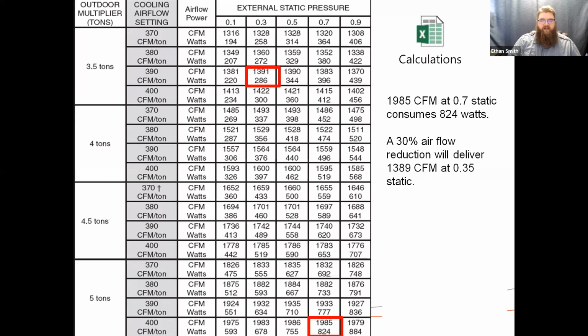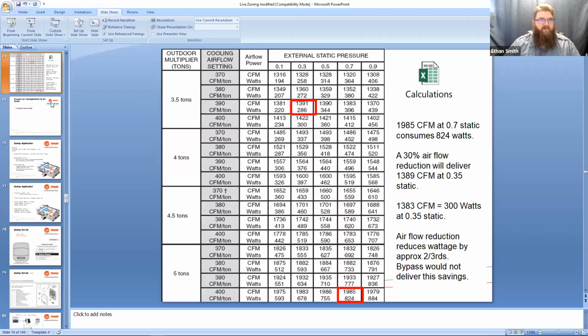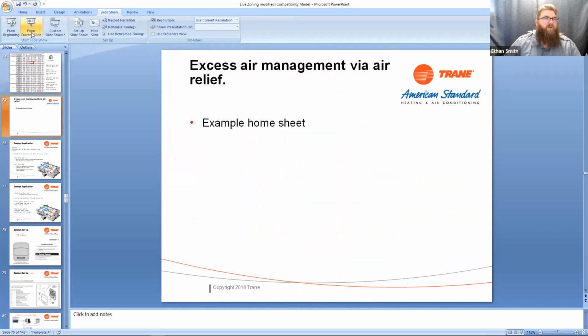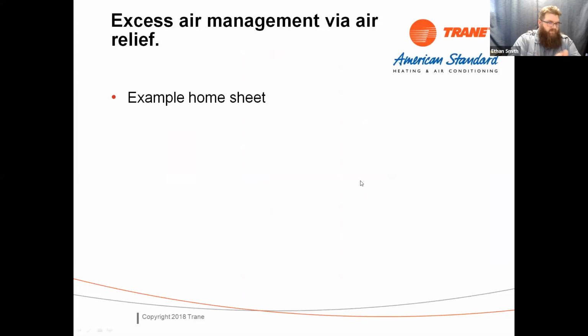So we can take that 1985 CFM, drop it 30% to 1391, and my blower usage goes from 824 watts to less than 300 watts. Okay. So now I've managed my excess air problem. And I've managed to save 60% power. I got 60% power savings, maybe a little less. Okay. So now I'm managing my excess air and I'm running efficiently. This does not cause me to lose capacity on my equipment at all, or lose efficiency on the equipment. So that's one way we can do it.